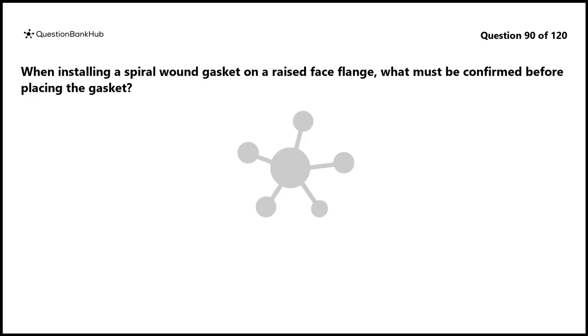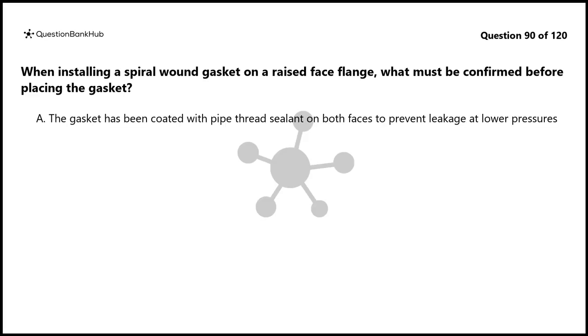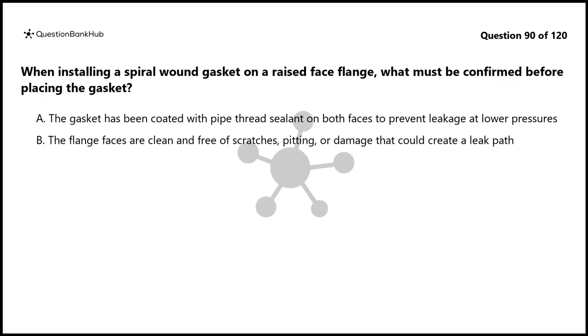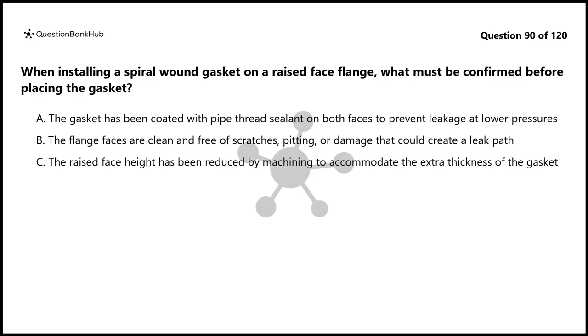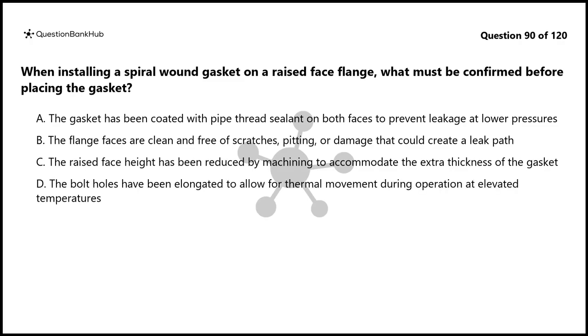Question 90. When installing a spiral wound gasket on a raised face flange, what must be confirmed before placing the gasket? A. The gasket has been coated with pipe thread sealant on both faces to prevent leakage at lower pressures. B. The flange faces are clean and free of scratches, pitting, or damage that could create a leak path. C. The raised face height has been reduced by machining to accommodate the extra thickness of the gasket. D. The bolt holes have been elongated to allow for thermal movement during operation at elevated temperatures.